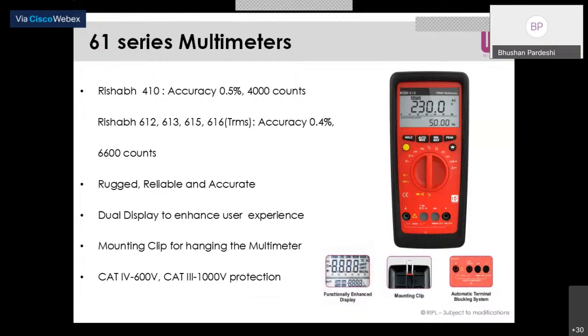If a higher surge comes during measurement, it can lead to burning or bursting of the instrument, and can also harm the user. So Rishabh provides two-way safety with a rubber holster as well as higher Cat protection whenever in use. This Cat protection is as per the standard IEC 61010-1, which is the safety standard used for category protection.